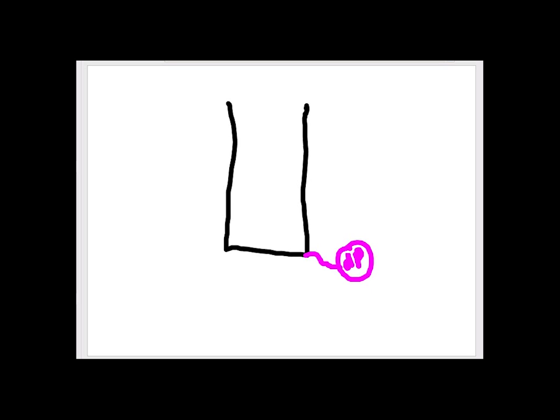I would never ever advise anybody to use what was called a flange-mounted DP, mounted on the side of the tank like that. The reason I would never advise anyone to use it is because I knew that when the diaphragm went wrong and the pressure sensor went wrong, you had to drain the tank.